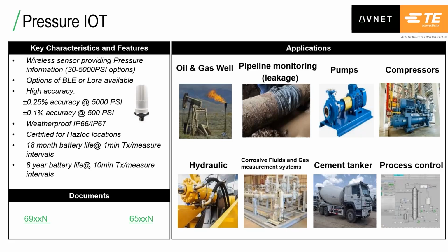On the pressure side, the new TE6 series of high-precision wireless pressure transducers eliminates the need for hard wiring, providing remote process control and monitoring through seamless digital communication. Our products are certified for intrinsically safe hazardous locations. They meet all applicable requirements for radio frequency communications and are CE and RoHS compliant. These high-accuracy sensors are enclosed in a stainless steel and polymer housing. Wireless pressure transducers are suitable for liquid, gas, contaminated, and mildly corrosive fluid measurements. The port design uses no internal O-rings or organics exposed to the pressure media, which provides excellent durability and long-term performance.